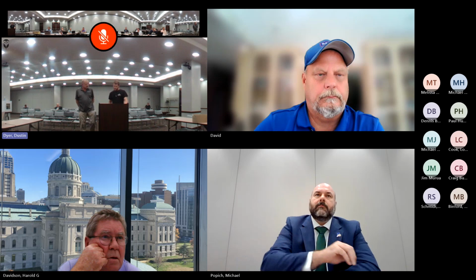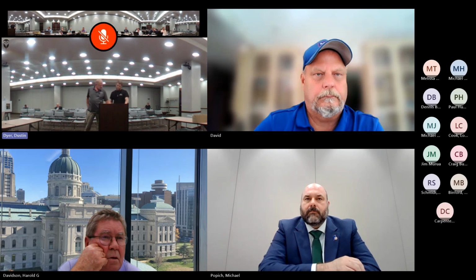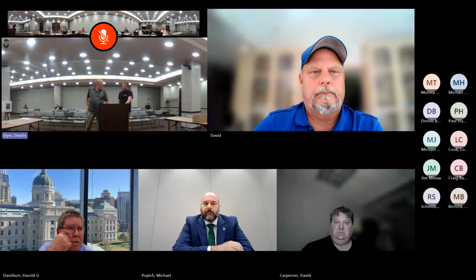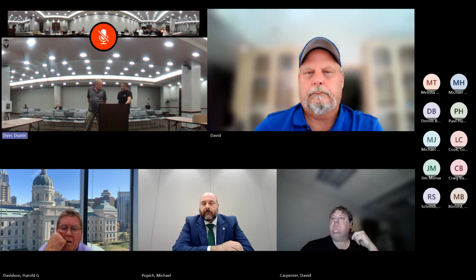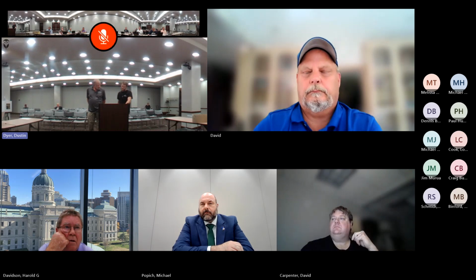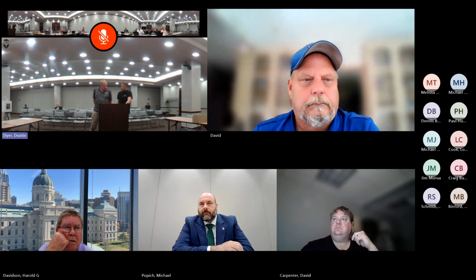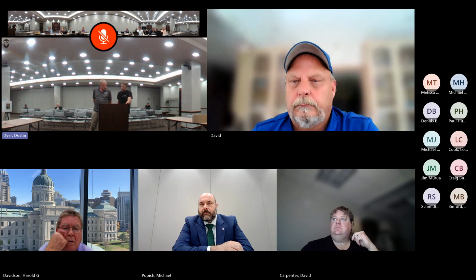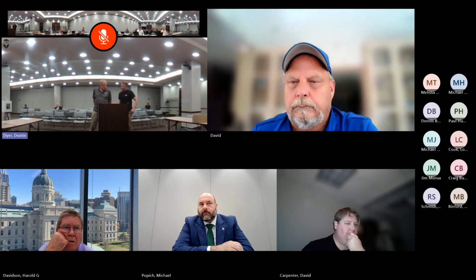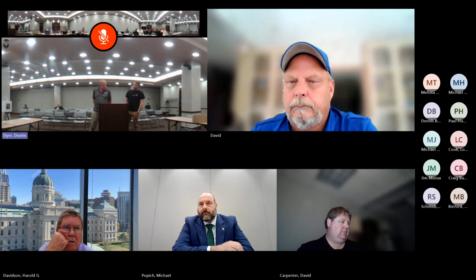When I got digging on this, I found a section, 903.3.1.1.1, that says: exempt locations — automatic sprinklers shall not be required in the following rooms or areas where such rooms or areas are protected with an approved automatic fire detection system in accordance with section 907.2 that will respond to visible or invisible particles of combustion.